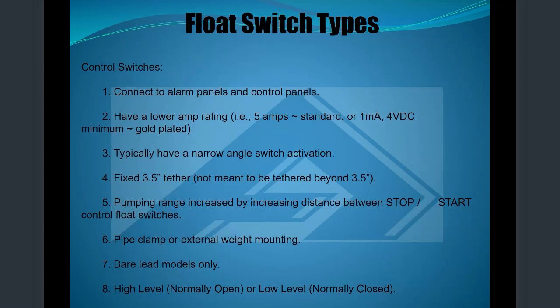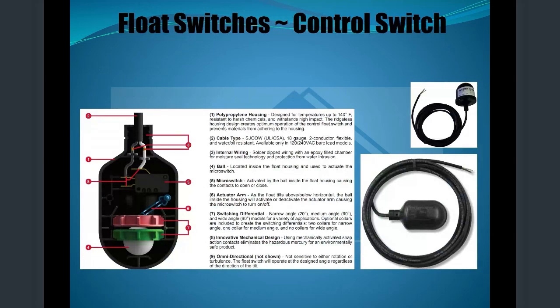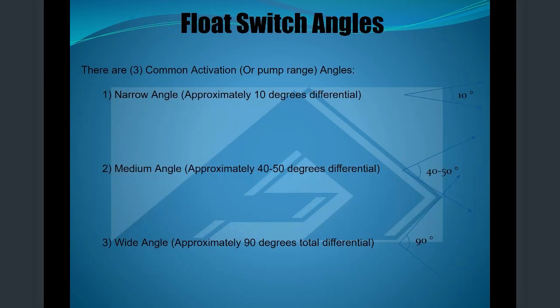Okay, next slide. Control switches, they control alarm or control panels. They have a lower amp rating, typically a narrow angle activation, and a fixed tether length. And the pumping range is increased by the distance between your start and your stop, because on a control float, you have a start and a stop versus one typically. Next, bare leads always, so you'd never have a piggyback. And those are the internals of that.